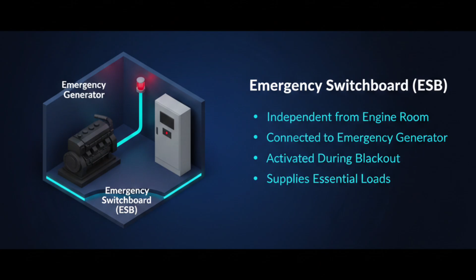The emergency switchboard does not supply full ship load; it supplies only essential loads required for safety. These include emergency lighting in accommodation and machinery spaces, navigation lights and bridge equipment, communication systems like GMDSS, fire detection and alarm systems, and sometimes steering gear and emergency fire pump.